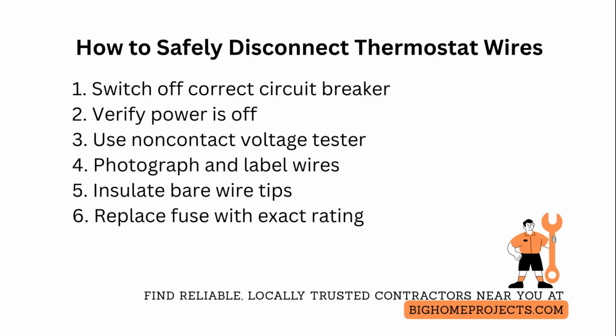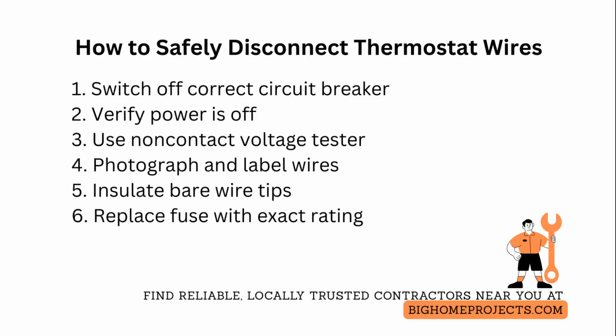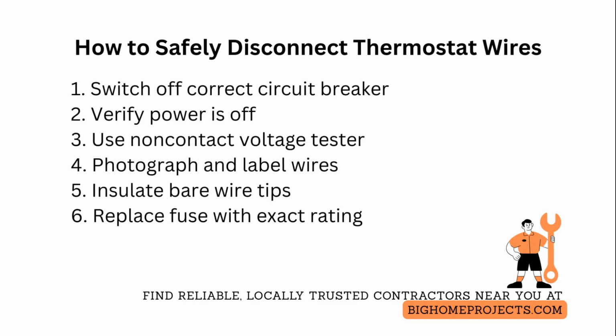Photograph the existing wire labeling and terminal layout, then label each conductor with tape and a marker so you can restore them exactly. Note common labels like red for power, white for heat call, yellow for cooling call, green for fan, and common or blue for the 24-volt return.